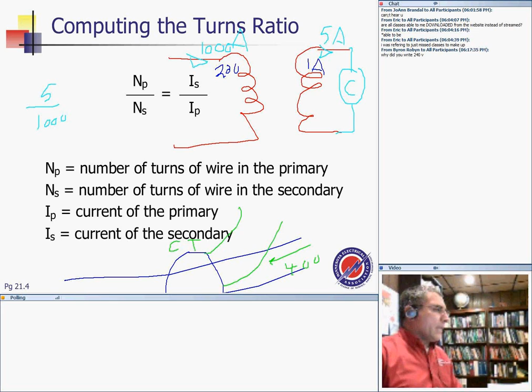If you have a 4000 amp bus switch here, how do we measure a 4000 amp switch? You're not going to put it through a coil. What you do is you have a CT. You familiar with the CT, the current transformer? I take this. Here's my bus. The current right in here is 4000 amps. You take 4000 amps and change it into 5 amps. What that means is every time there is 4000 amps going through the bus, it will be seen on the secondary of that CT as 5 amps.